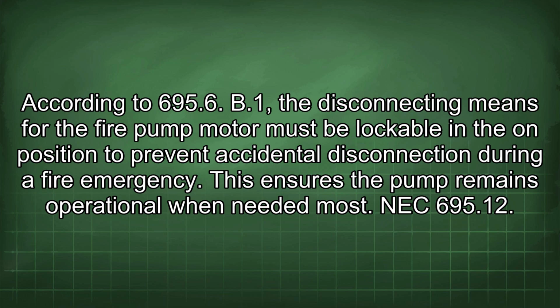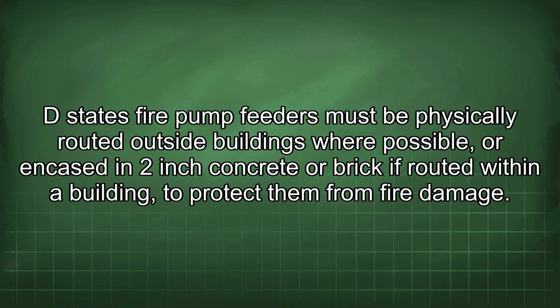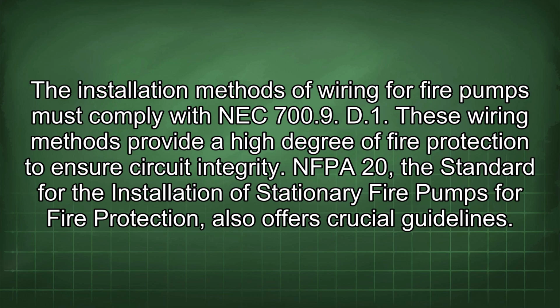NEC 695.12 states fire pump feeders must be physically routed outside buildings where possible, or encased in 2-inch concrete or brick if routed within a building to protect them from fire damage. The installation methods of wiring for fire pumps must comply with NEC 700.9 D.1. These wiring methods provide a high degree of fire protection to ensure circuit integrity.